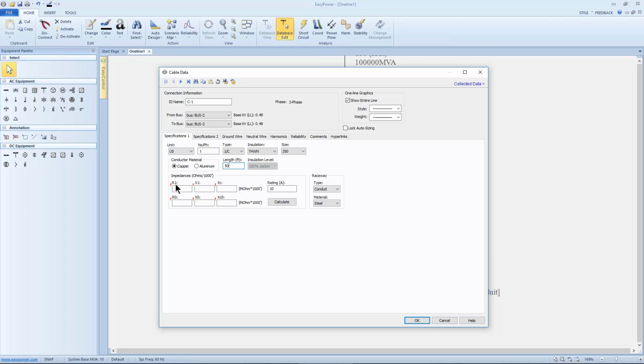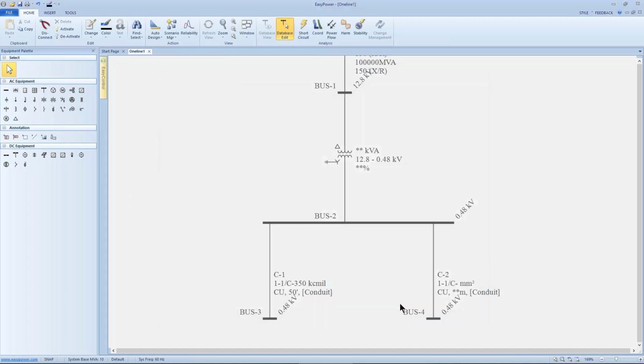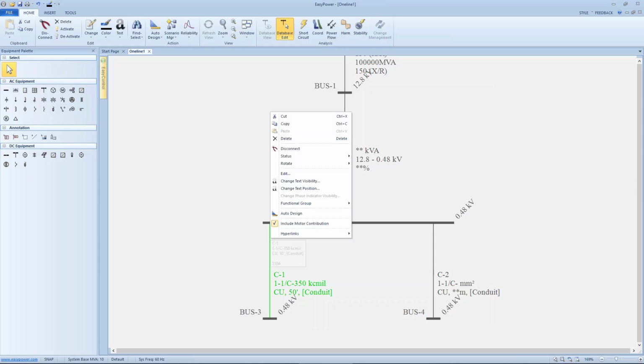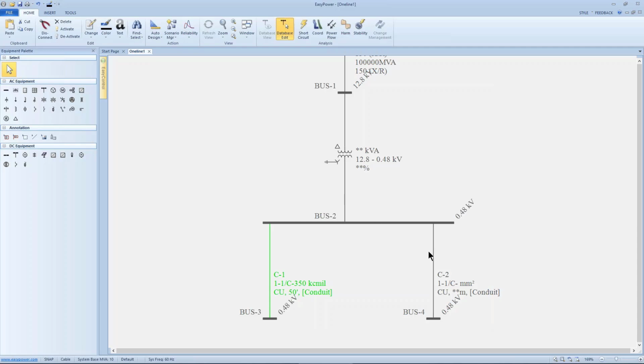Now these red exclamation points indicate that there's missing data. If I use the calculate button, the tool will calculate the ampacity for this particular cable and the resistive and reactive impedance per 1,000 feet. So I'm going to click OK to save these results. Now I'm going to right click on this first cable again and copy. Right click on the second cable and paste, and all that data is taken to the second cable.